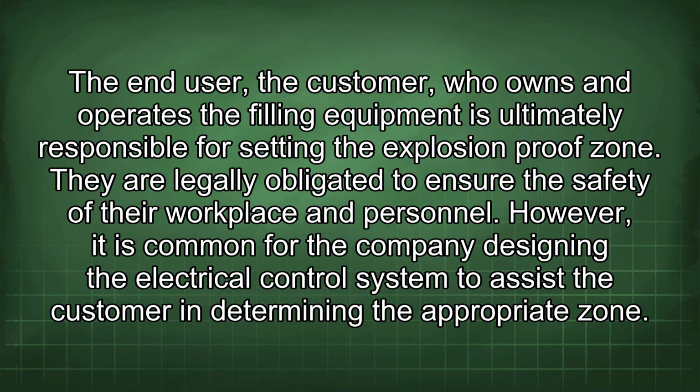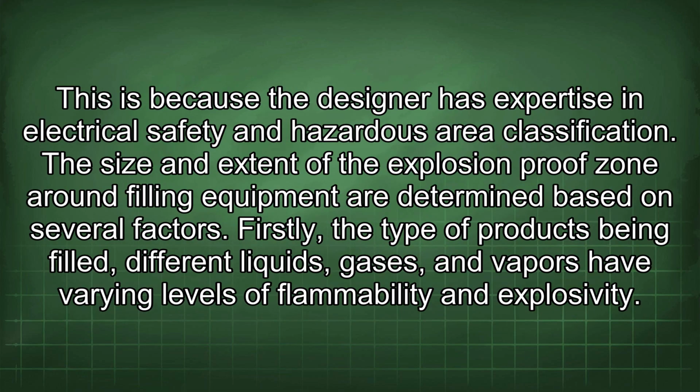The end user, the customer, who owns and operates the filling equipment, is ultimately responsible for setting the explosion-proof zone. They are legally obligated to ensure the safety of their workplace and personnel. However, it is common for the company designing the electrical control system to assist the customer in determining the appropriate zone. This is because the designer has expertise in electrical safety and hazardous area classification.